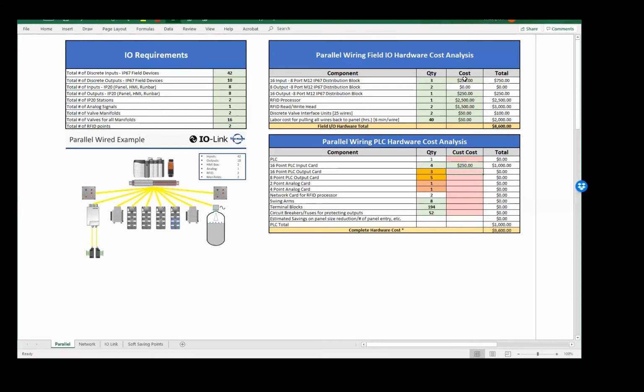All right, perfect. Again, the output PLC card, if we're using a 16-point, we need three of them, or five if we're using an 8-point. We'll use the 16-point, and we'll say the market cost is $250 for those. All right, perfect. Zero out the cost of the 8-point. We do have an analog, so we are going to use an analog card. Not an inexpensive piece of hardware for a PLC. Right, John? Oh, they're very expensive. That's the number one thing: hey, how do we get rid of that card? Yeah, so right there to handle two analog signals, we're looking at $650.